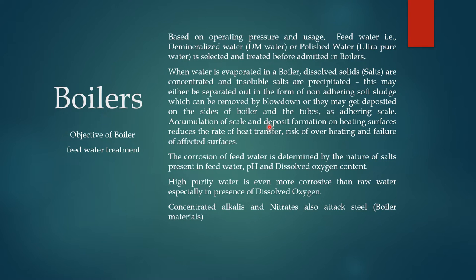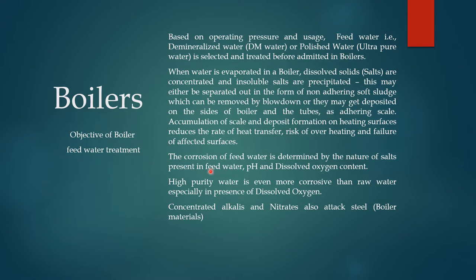Alternatively, scale and deposits may form on the sides of the boiler and tubes. This accumulation of scale on heating surface areas reduces the rate of heat transfer, creating a risk of overheating and failure of the affected surfaces. If scale formation is present, heat transfer is reduced, and if the flame directly impinges inside the furnace, it can lead to bulging or failure of that area. Corrosion will also occur.